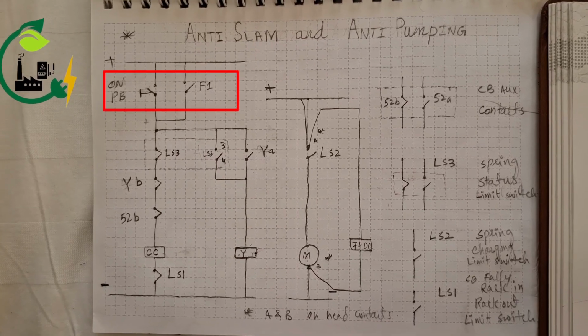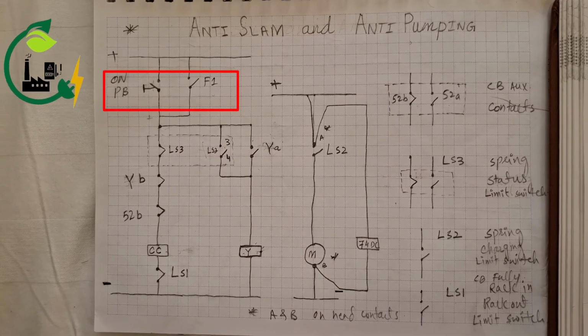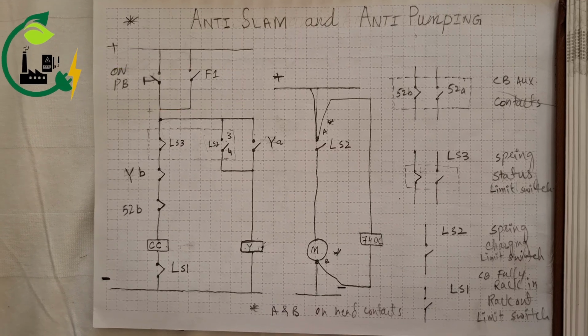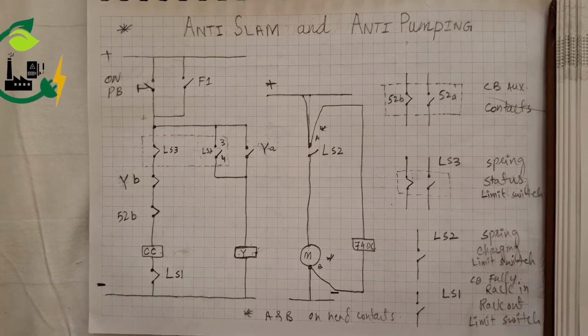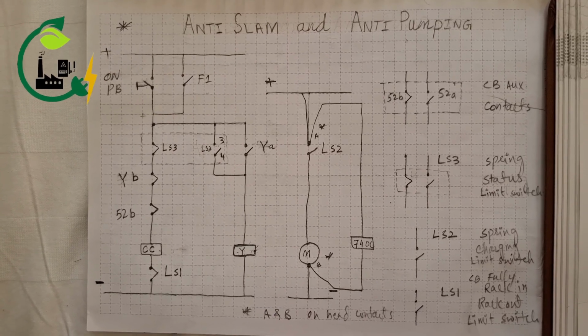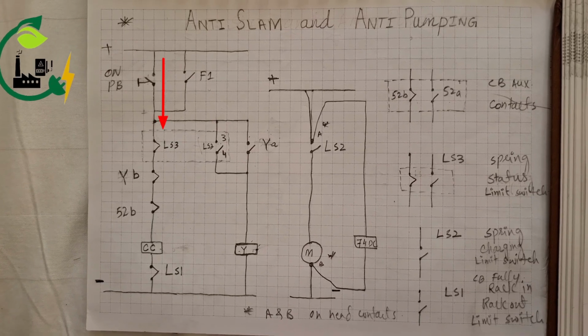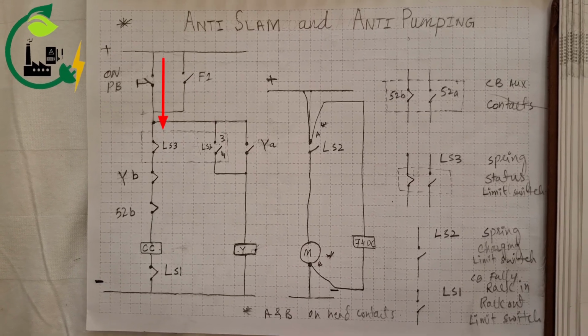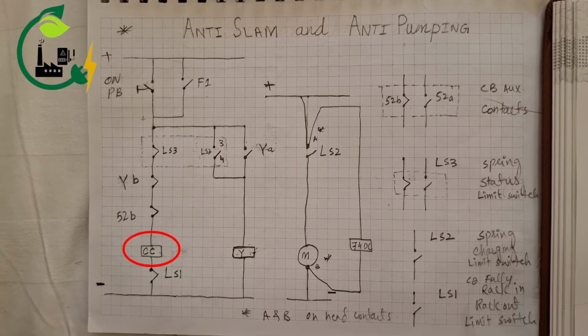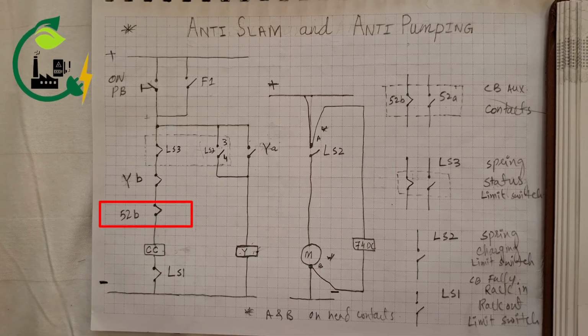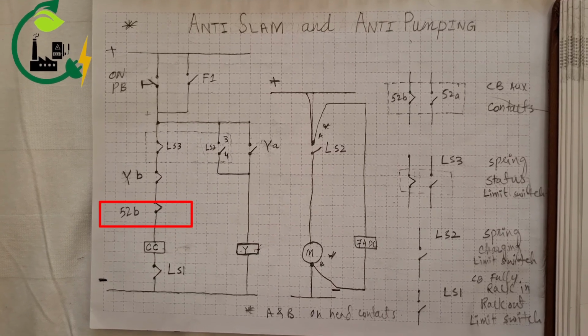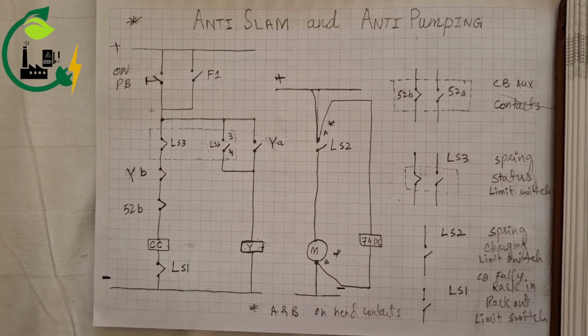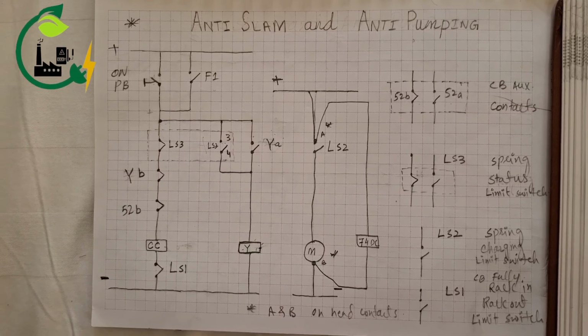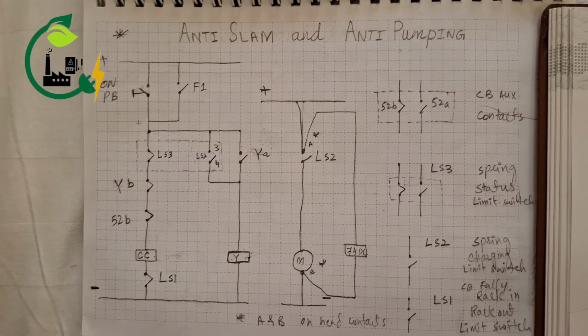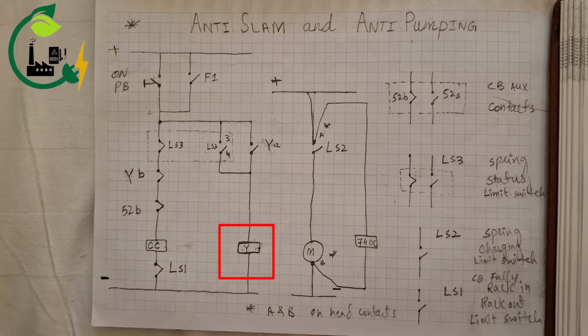If due to any reason this push button or the BCU contact F1 is latched, and we did not put the anti-slam contact, the supply will remain on the closing coil and can damage our closing coil. So to protect our closing coil, we put this anti-slam contact in the closing circuit. But what is the purpose of the anti-pumping relay?